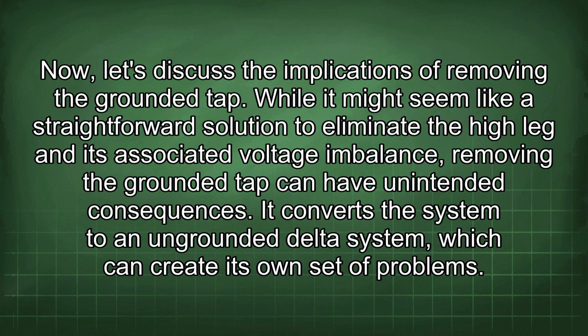While it might seem like a straightforward solution to eliminate the high leg and its associated voltage imbalance, removing the grounded tap can have unintended consequences. It converts the system to an ungrounded delta system, which can create its own set of problems.